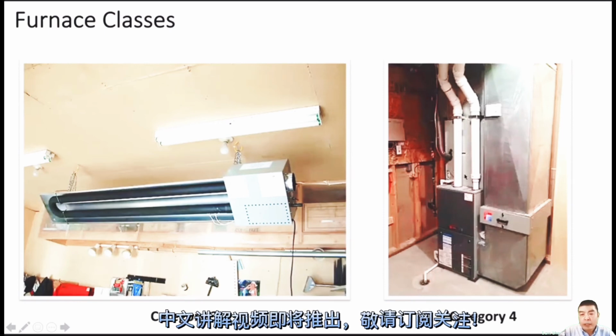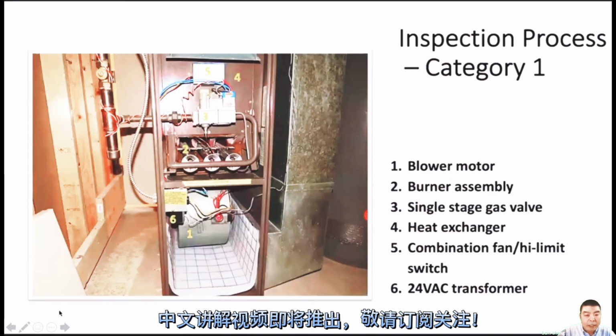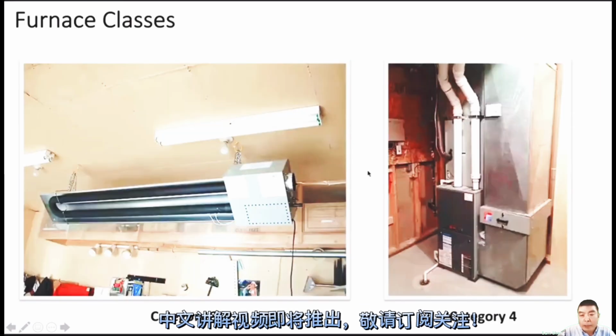In Saskatchewan the gas code requires an inspection door just above the furnace. Between the furnace and the A coil, we should make an opening when we install the furnace. So if we need to check the heat exchanger, we just open that access door and then we can see inside.